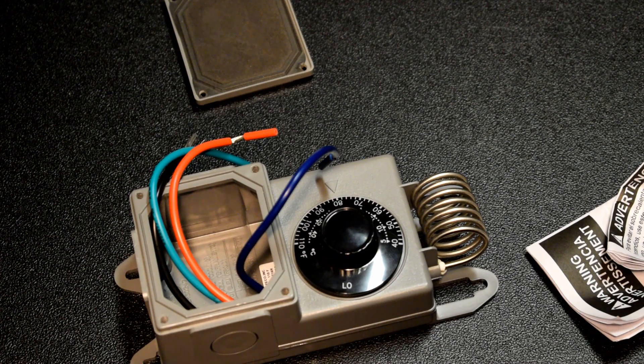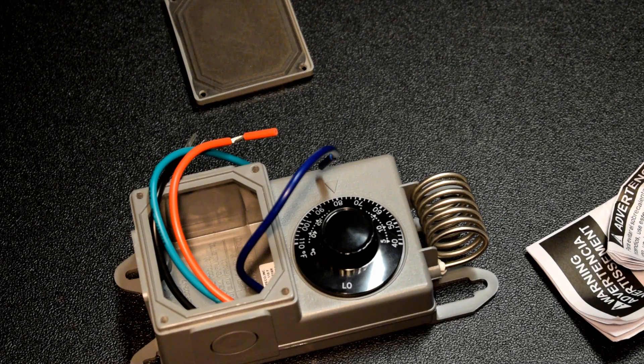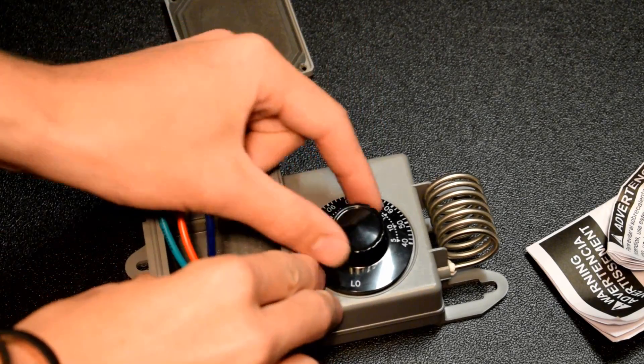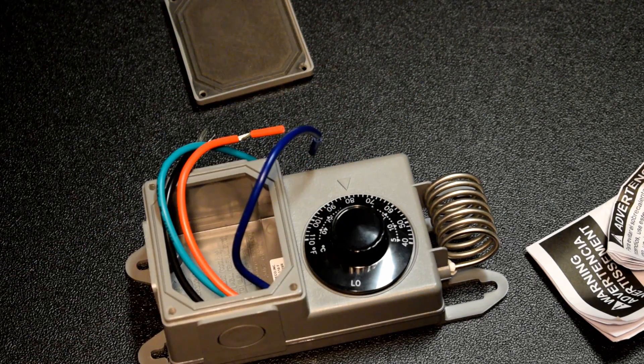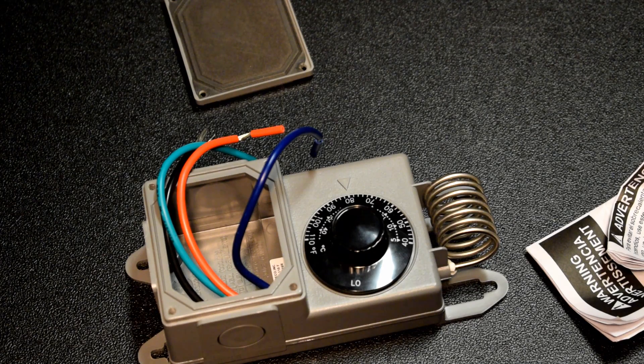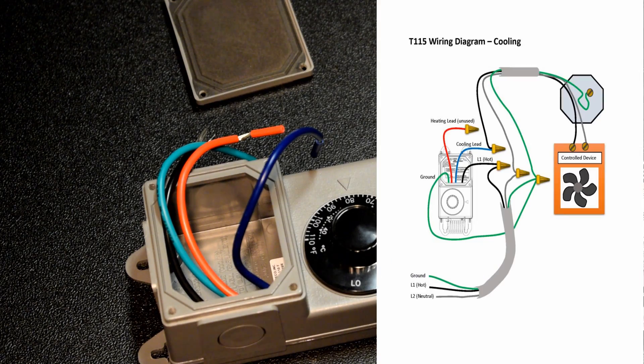So if you wanted a fan to come on at 80 degrees in your greenhouse to cool the greenhouse down, you'd put power into the black wire, tie the fan off to the blue wire, cap the red wire off. That way, when a cooling demand was required, the blue wire would be powered and the fan would be on.